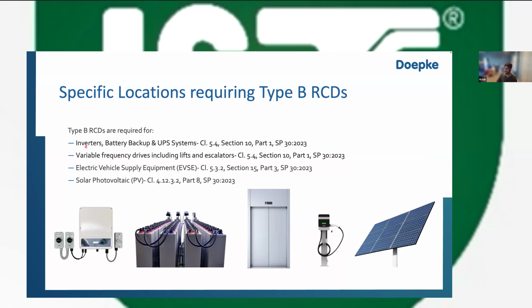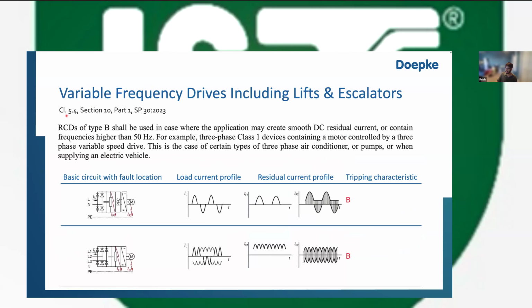But what are the actual applications that are mentioned in the National Electrical Code? We care about what's there because that's what's referenced in the lift standard. It has type B RCDs are required for inverter, battery backup, UPS systems, variable frequency drives, including lifts and escalators, which is mentioned in clause 5.4, section 10, part 1 of the National Electrical Code. Also EVSE, so EV and solar PV. But again, if I look at what's written in clause 5.4, it says RCDs of type B shall be used in case where the application may create smooth DC residual current or contain frequencies higher than 50 Hz. For example, 3-phase class 1 device containing a motor controlled by 3-phase variables.